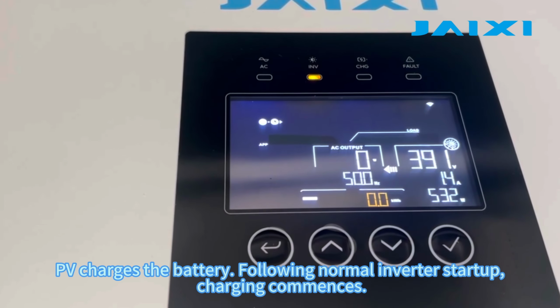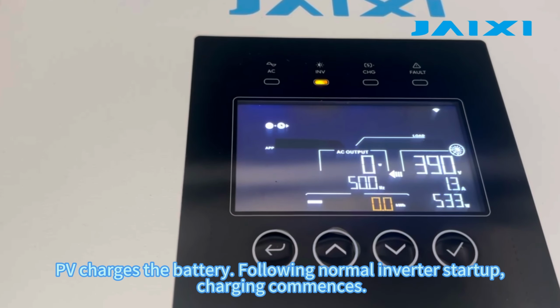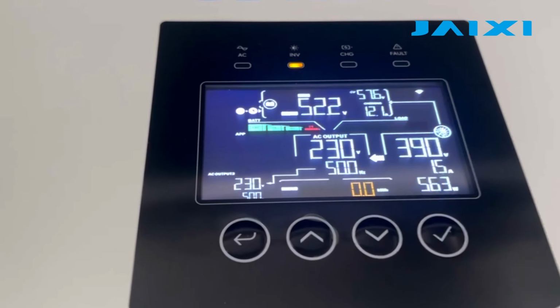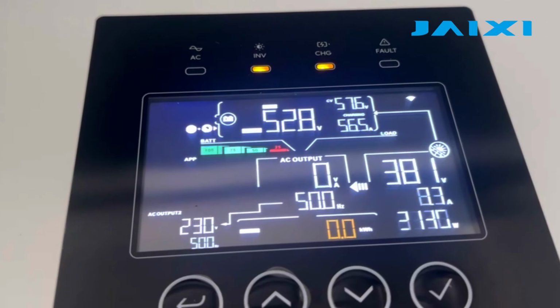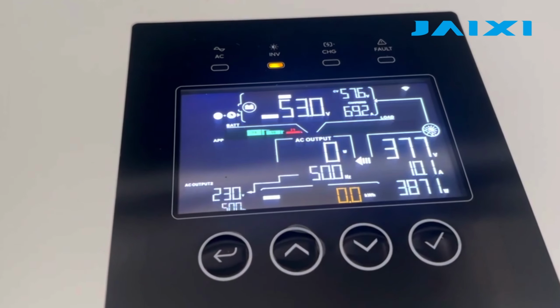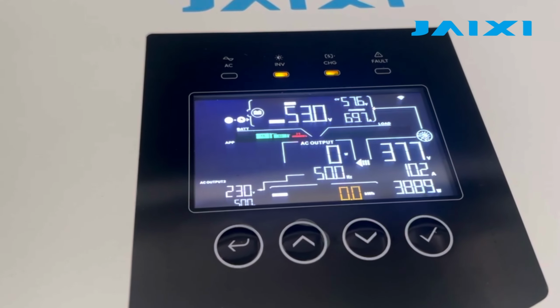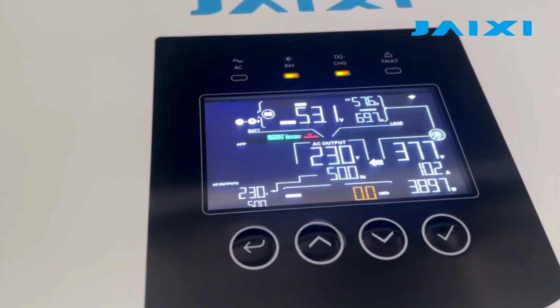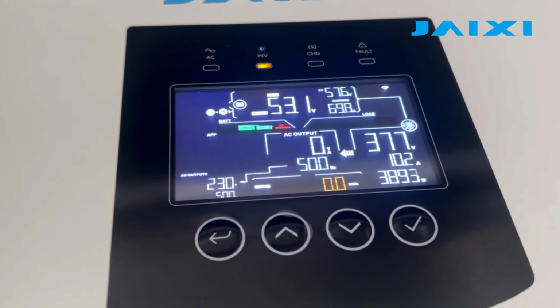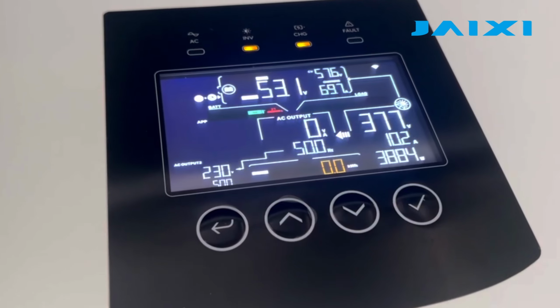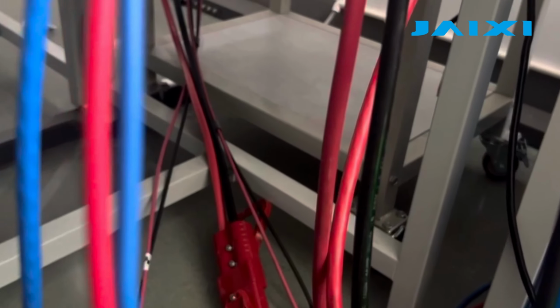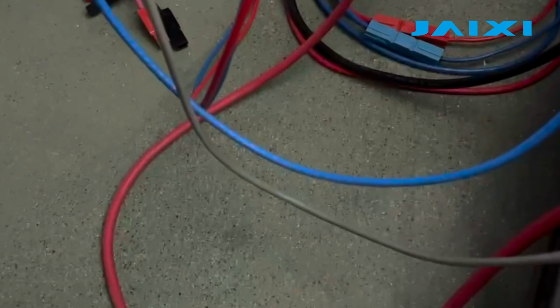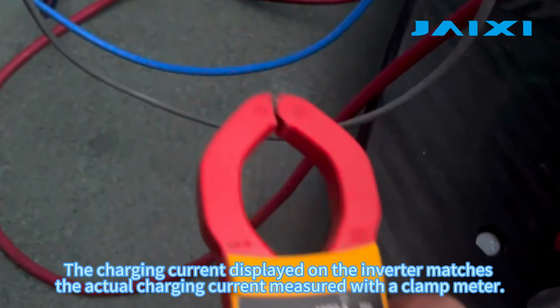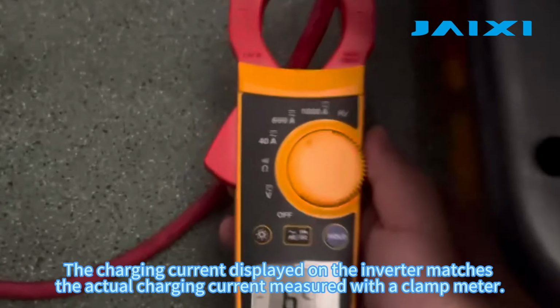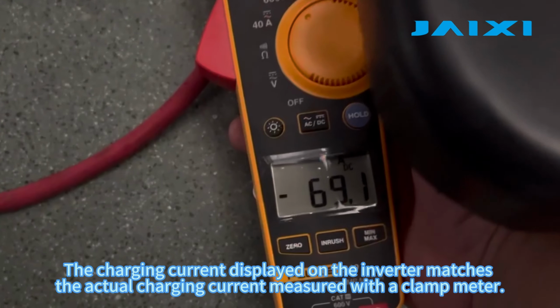PV charges the battery. Following normal inverter startup, charging commences. The charging current displayed on the inverter matches the actual charging current measured with a clamp meter.